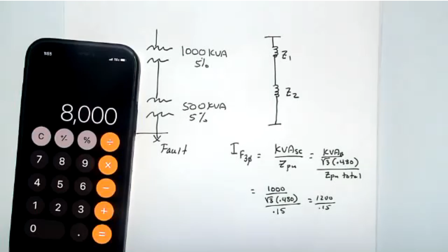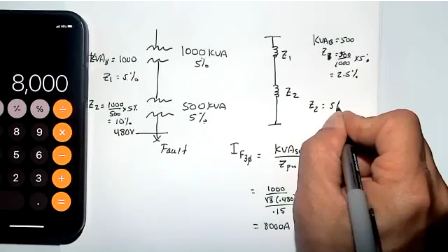Now, I'm going to show you that it would be the same if we went the other way. Let's say our kVA base is 500 kVA. Z1, again, delivers less impedance at that 500 kVA base. So Z1 would be 500 divided by 1000 times 5%, and we end up with 2.5%. Z2 at 500 is still 5%. Then we add those two together.